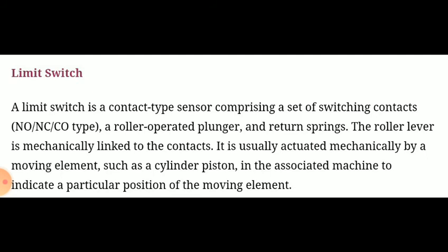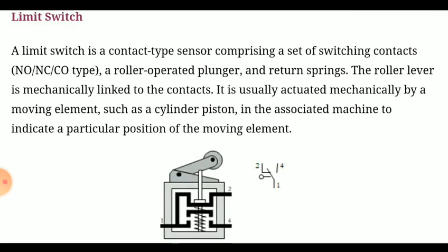A limit switch is a contact type sensor comprising a set of switching contacts, normally open, normally closed, and CO type, that is changeover type, a roller operated plunger and return springs. The roller lever is mechanically linked to the contacts. It is usually actuated mechanically by a moving element such as a cylinder piston in the associated machine to indicate a particular position of the moving element. Then limit switch.